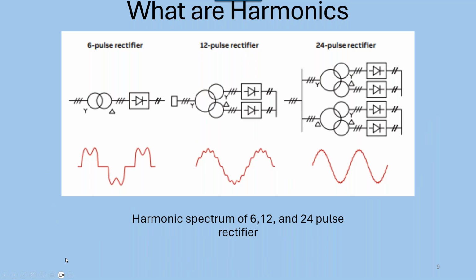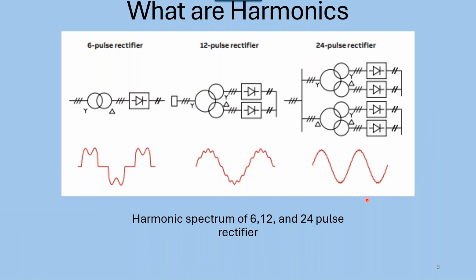have transformers. Let me go back and put my laser pointer back. So here you see these transformers. What we do with these transformers is we have a transformer in front of it, and we do a phase shift. By shifting the different phases, you can actually cancel out the harmonics. And that's what they're doing in a 24-pulse rectifier.